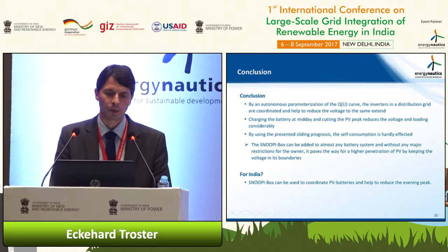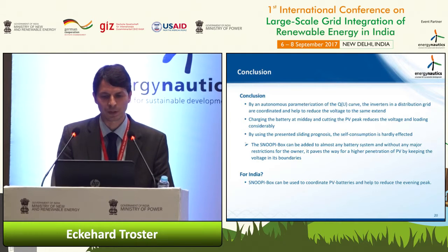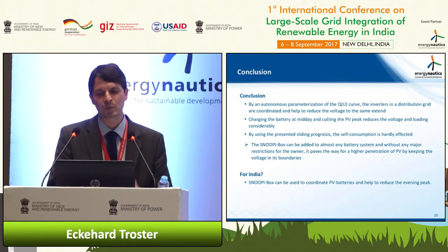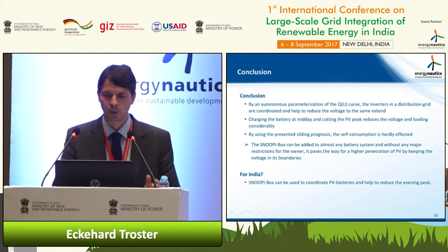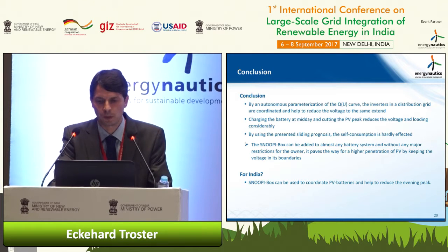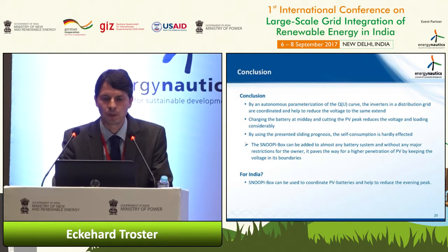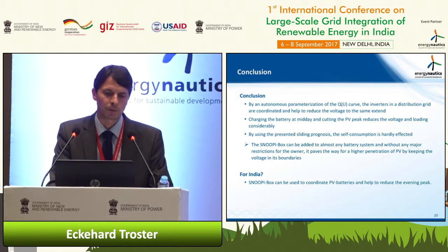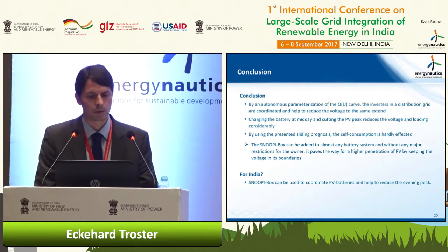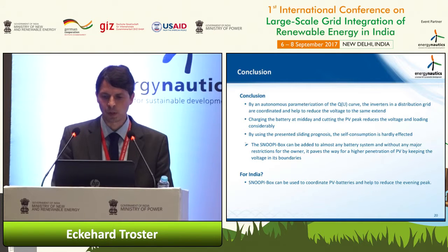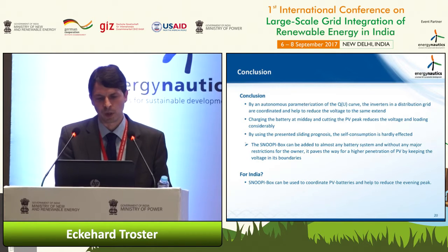Secondly, we can coordinate it with regard to cutting the PV peaks in order to reduce the voltage, and at the same time this also reduces the loading, because voltage and loading typically have very high correlation in these feeders. And by using this sliding prognosis, or persistence prognosis as we call it, the self-consumption itself was hardly affected.